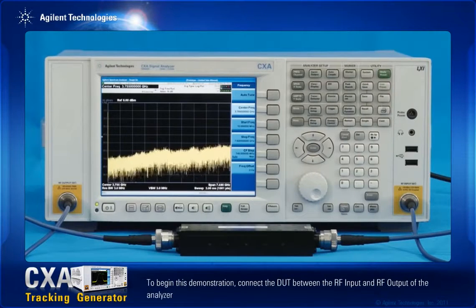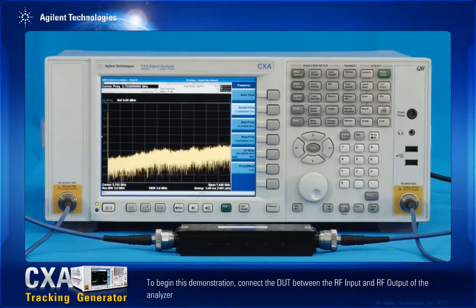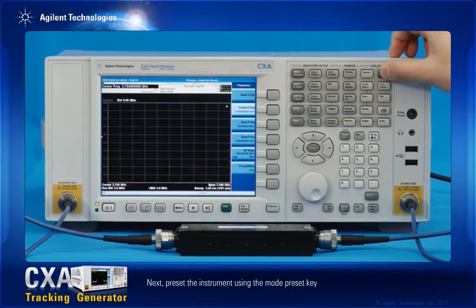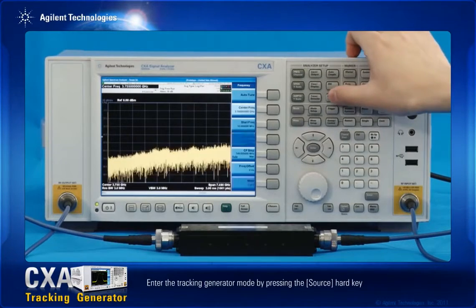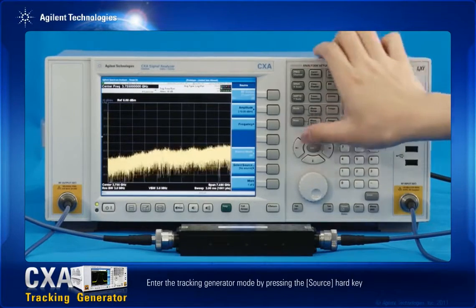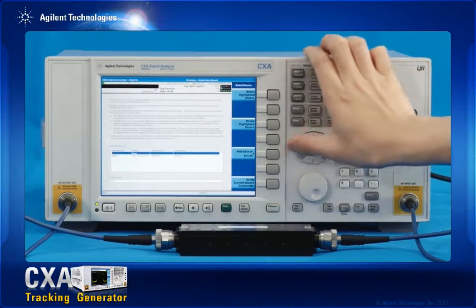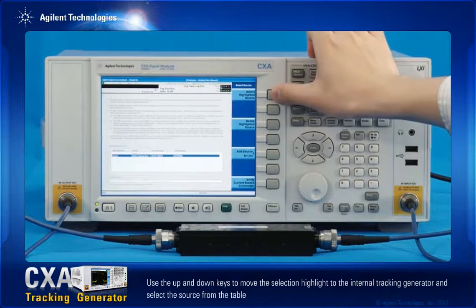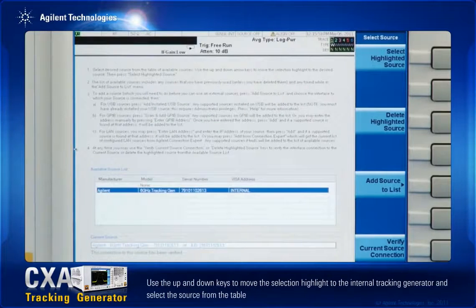To begin this demonstration, connect the DUT between the RF input and RF output of the analyzer. Next, preset the instrument using the mode preset key. Enter the tracking generator mode by pressing the source hard key, then use the up and down keys to move the selection highlight to the internal tracking generator and select the source from the table.